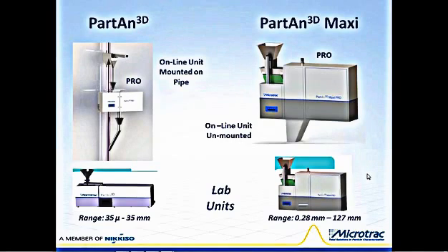The online Pro versions provide continuous, unmanned operation and sample measurement with turnaround time averaging about 10 minutes, which greatly improves process control response time with the normal increase in both productivity and quality versus having to collect the samples manually, bring them to a lab, and then go through making the manual measurements.